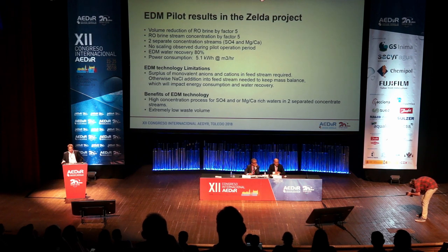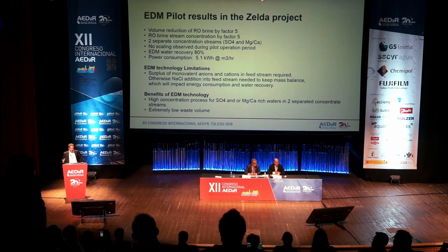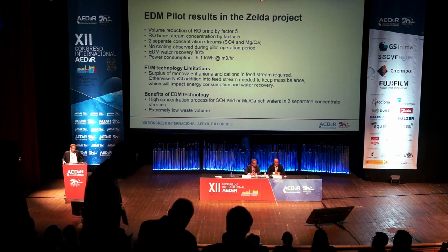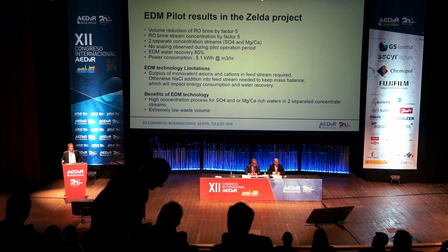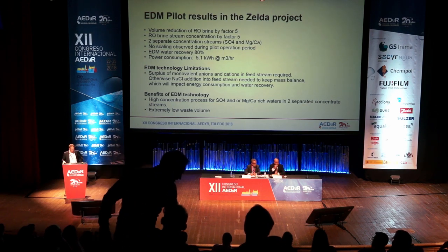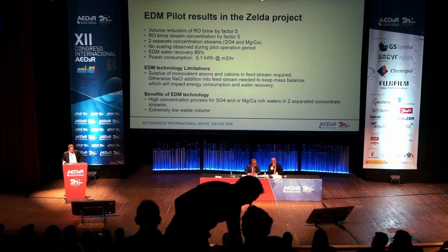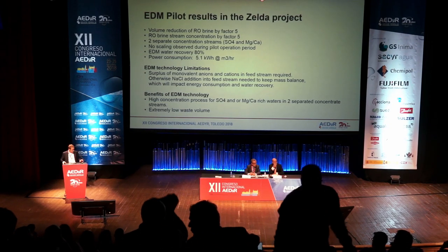Water recovery was about 80% with a power consumption of 5.1 kilowatt-hours per cubic meter. The limitation of this technology is that you need a surplus of monovalent anion and cation ions in the feed stream. If that's not the case, you have to dose sodium chloride addition to the feed stream to keep the mass balance — it can still work, but it will impact energy consumption and water recovery. The benefit is a high concentration process for sulfate and magnesium rich waters, separating into separate streams with extremely low wastewater volumes.